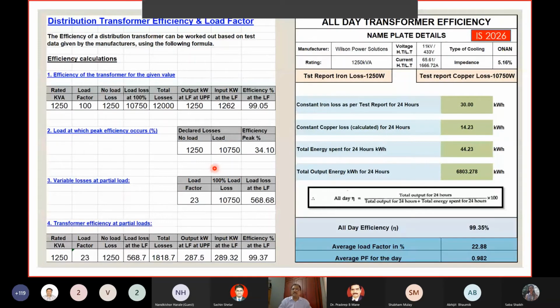And with this, we are calculating the all-day efficiency of a transformer. Now, this is not an industry, this is a hospital. Industries also, you have two kinds of industries. A textile industry will have 24 hours constant power. Whereas if you go to an engineering industry, the average load factor will be less than 50%. Some shifts will be very high energy, some shifts will be low energy. And there will also be long periods of rest in between shift changes and things like that. Whereas in the hospital, the requirement is continuous, 24 hours.